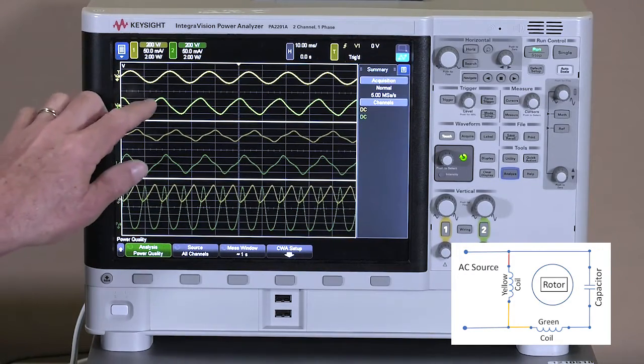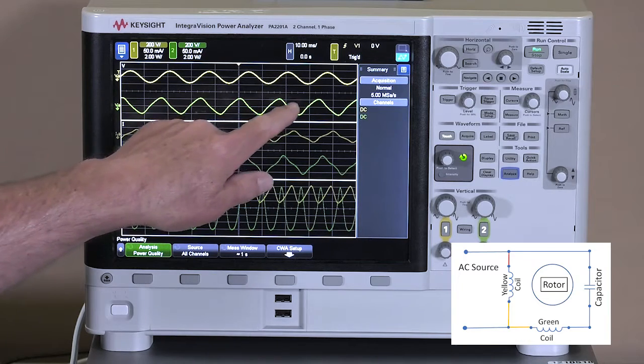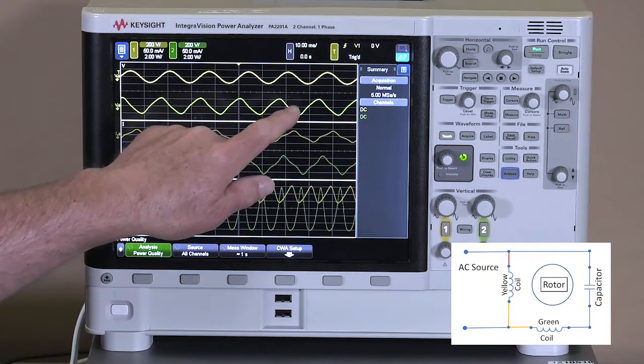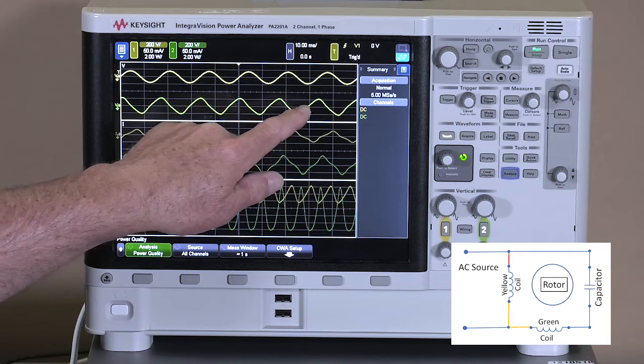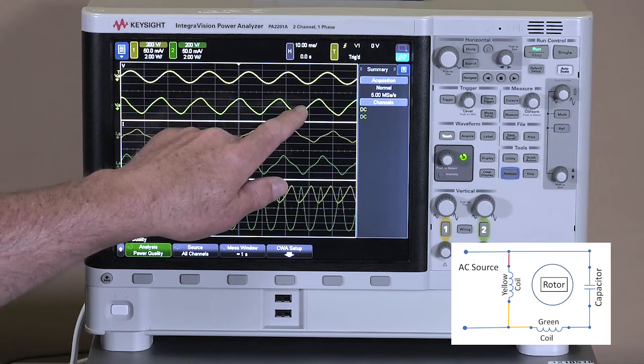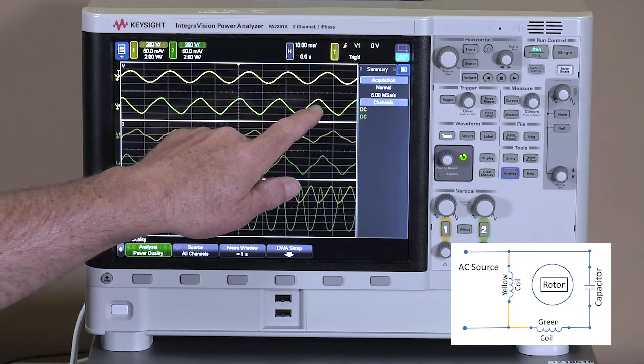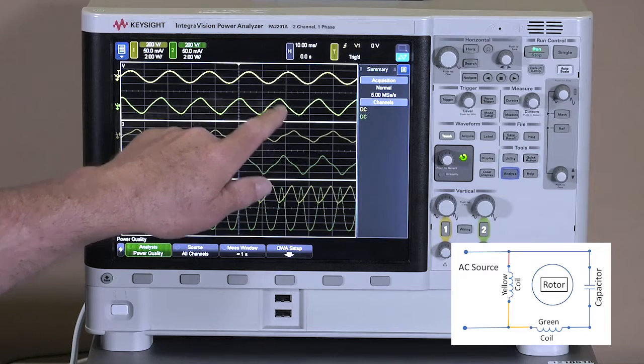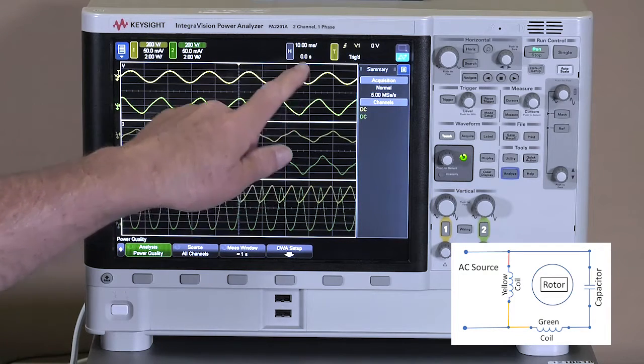The second coil is shifted by 90 degrees because of our capacitor. This capacitor is what's called a run capacitor, and its purpose is to shift the signal on the second coil by 90 degrees.